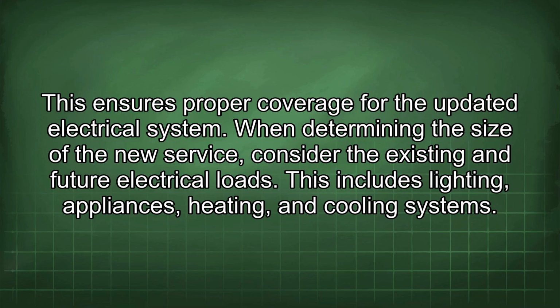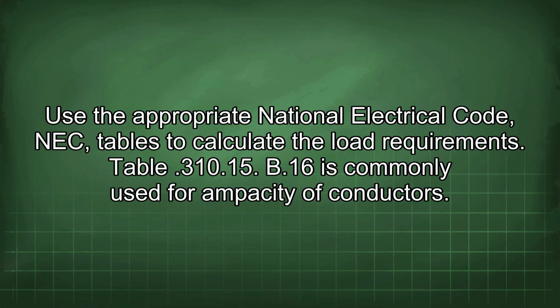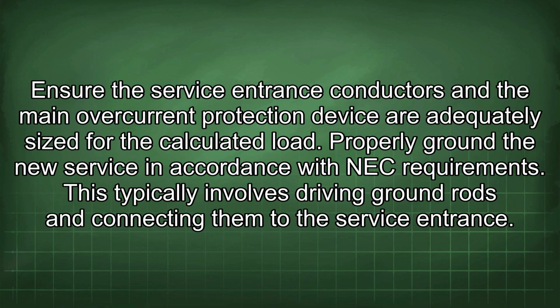When determining the size of the new service, consider the existing and future electrical loads. This includes lighting, appliances, heating, and cooling systems. Use the appropriate National Electrical Code (NEC) tables to calculate the load requirements. Table 310.15(B)(16) is commonly used for ampacity of conductors. Ensure the service entrance conductors and the main overcurrent protection device are adequately sized for the calculated load.